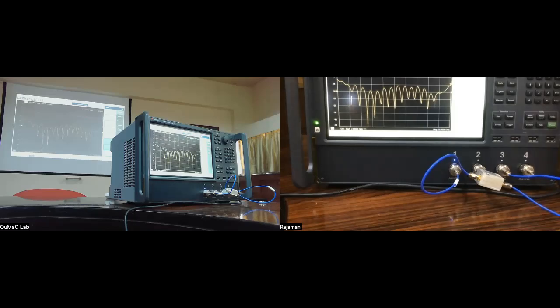So now I said something which I had not mentioned earlier, though I might have mentioned briefly. I'm now talking about the phase relationship between what is coming at the output. Right? Can we check that? Yes, we can, because the network analyzer allows us to measure phase. So far, we have only been looking at magnitudes. So now let's look at the phase as well.